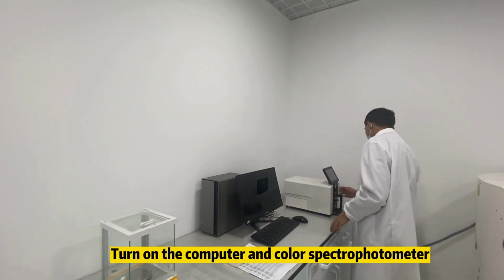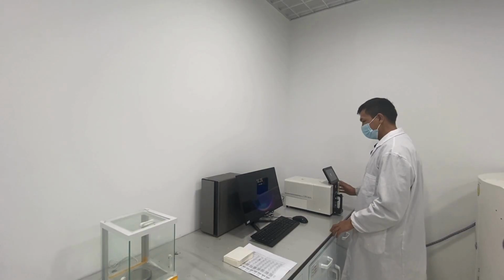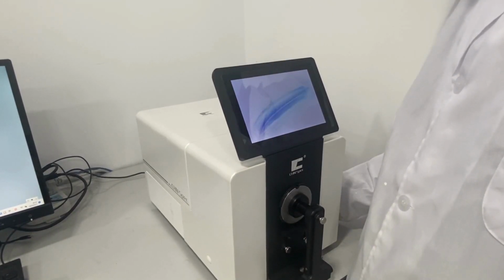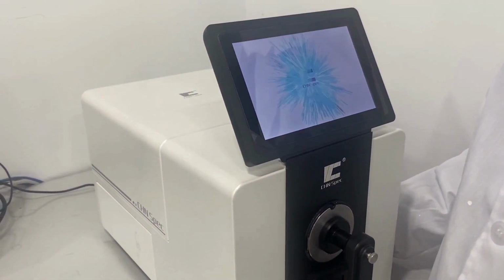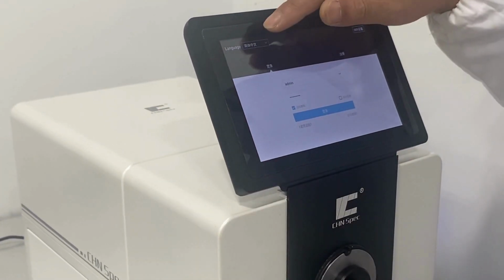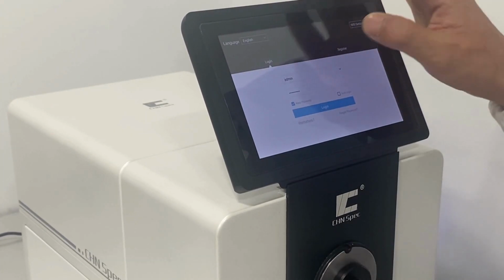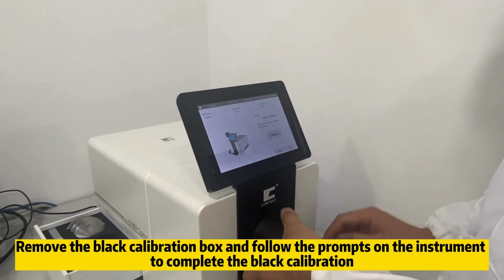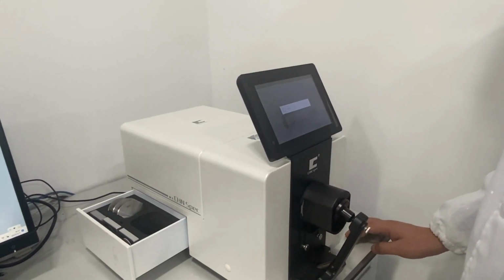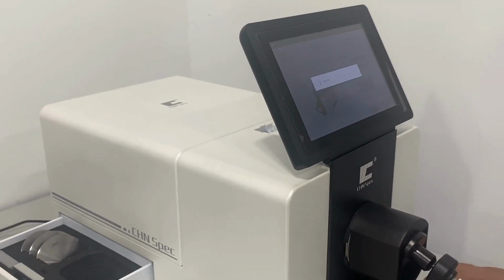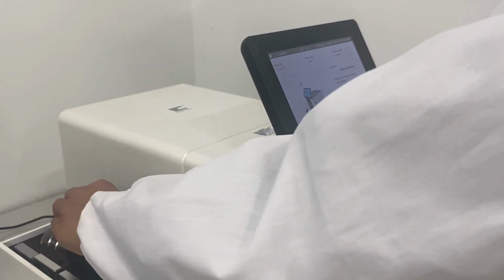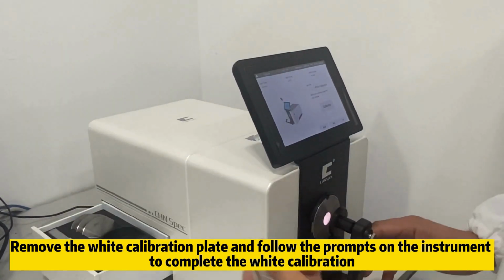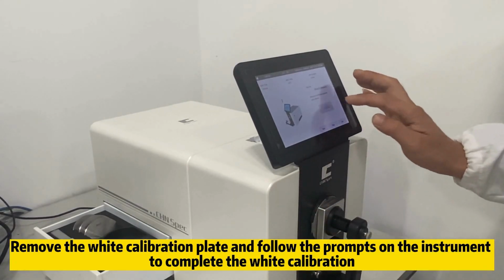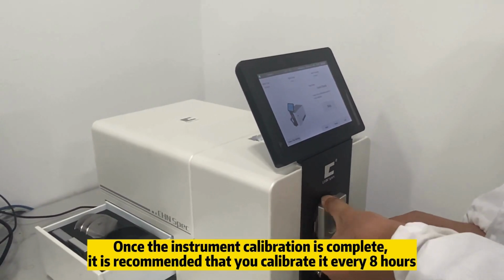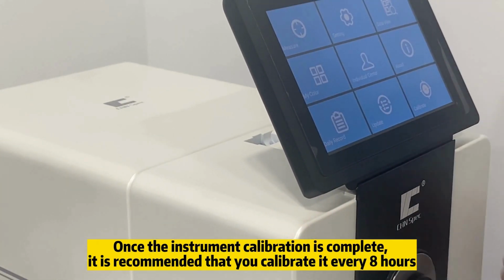Turn on the computer and the color spectrophotometer. Switch the instrument display language and click Login. Black and white calibration of the instrument. Remove the black calibration box and follow the prompts on the instrument to complete the black calibration. Remove the white calibration plate and follow the prompts to complete the white calibration. Once the instrument calibration is complete, it is recommended that you calibrate it every 8 hours.